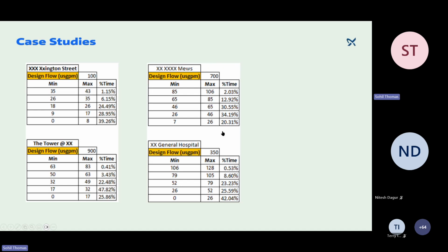But when we looked at the actual load profile, what we see is that the pump is not pumping more than 106 gallons. That's the peak flow. And that too, you see only around 2% of the total pump running time is where this peak load is operating. So where the actual pump working is happening, this 60 to 80% is happening even less than 10% of the actual design flow that was designed for.